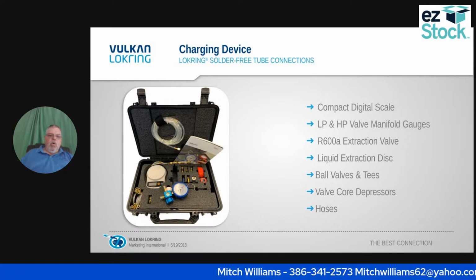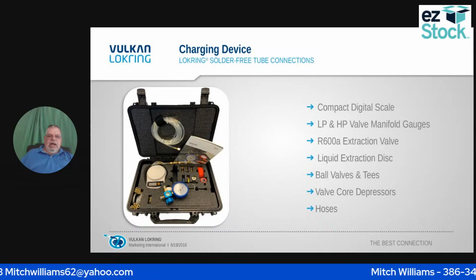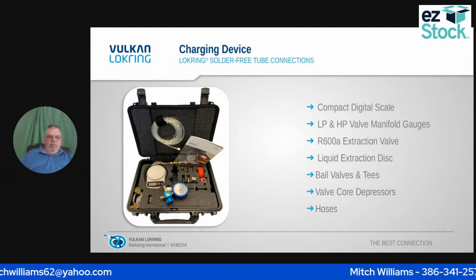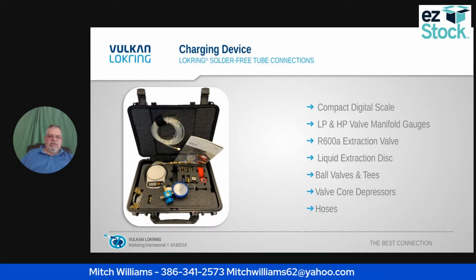Okay, so what comes in my LokRing kit? I have a compact digital scale. I have a low pressure and a high pressure manifold gauge. I have the R600a extraction valve. I have liquid extraction discs. I have ball valves and tees. I have the valve core depressors, and then I have hoses for my low pressure and high pressure manifold gauge. Okay, that's what comes in this recovery kit.